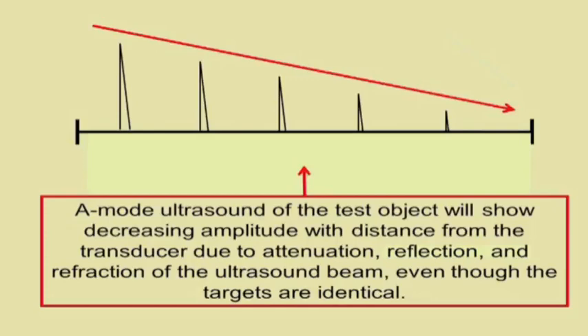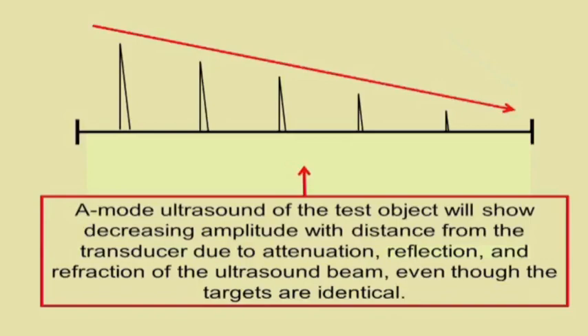So, okay, that's not a good thing. So the way you can work with that is actually on the receive end, you can ramp or boost the signal selectively so that the peaks come out pretty much equal. Now, obviously, we're going to introduce some noise and problems into the system, but that's the idea. This is what nature gives us where we're losing energy. We want to display it with roughly equal energy, and of course, what we're displaying is going to be B images, not spikes, but the spikes are the basis for the B images.